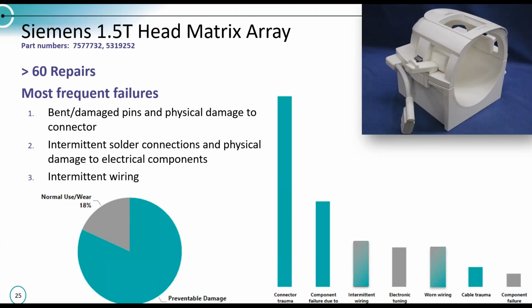Another type of head coil that we see come in a lot, and again, a multi-piece design. So different pieces and components of this coil mesh together. And so we're seeing physical damage to pins or connectors that interlock between the different components as well as the connector itself. Again, connector damage, component failures due to trauma, and this probably has one of the highest preventable damages coming into our facility. About 82% of the coils coming in arrive as a result of preventable damage.